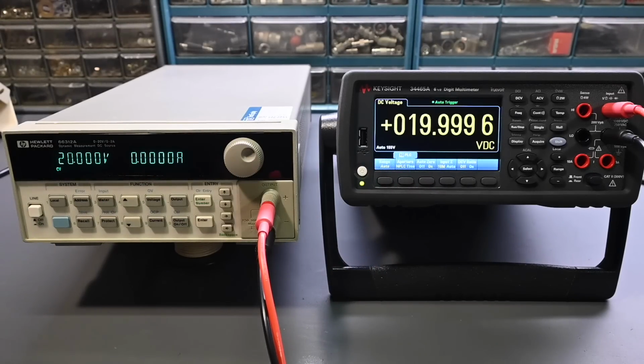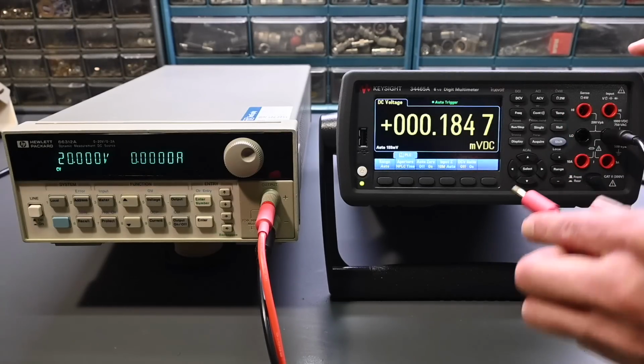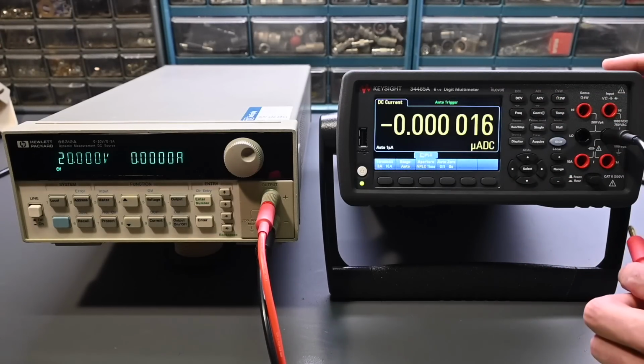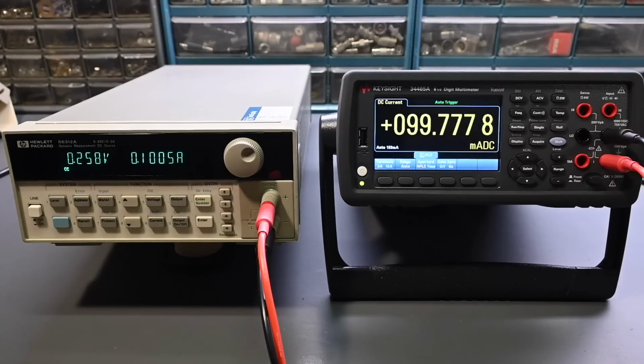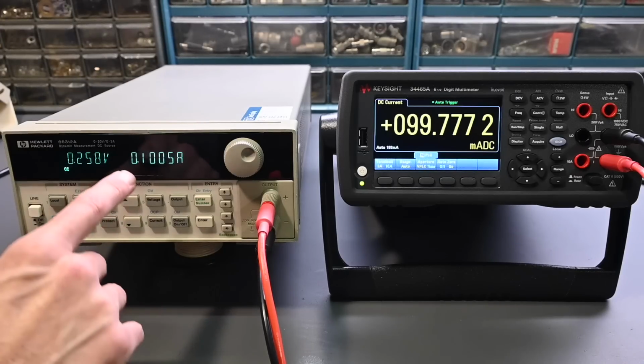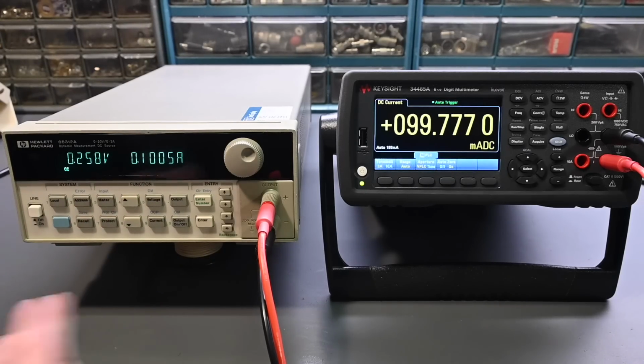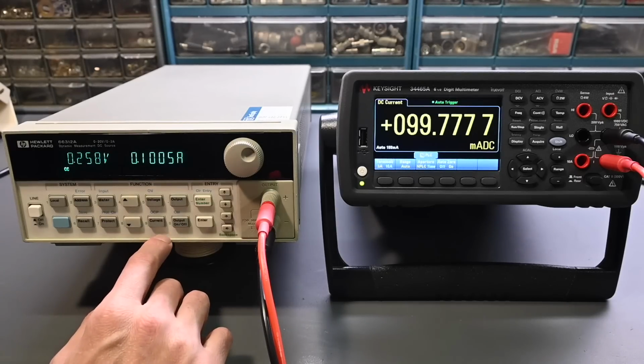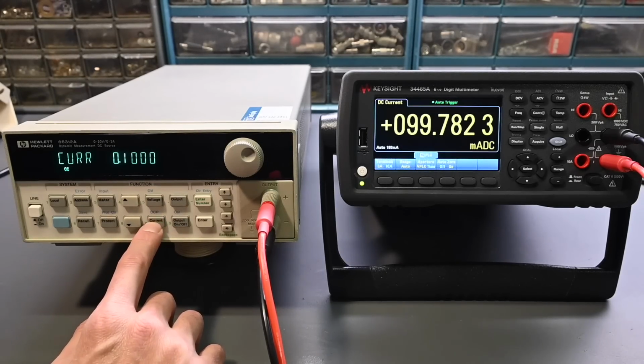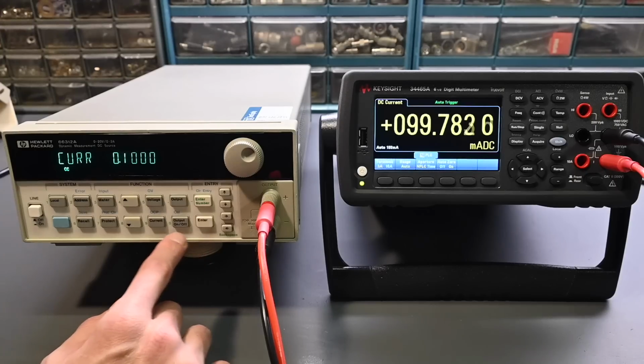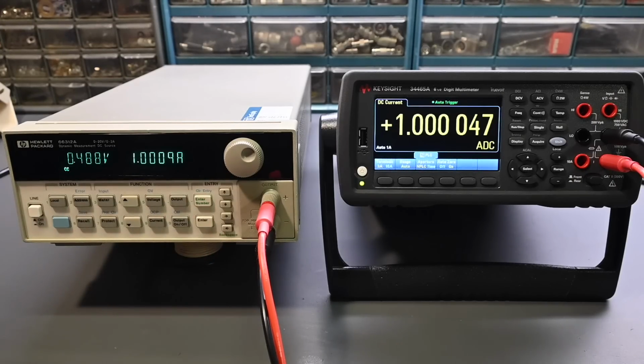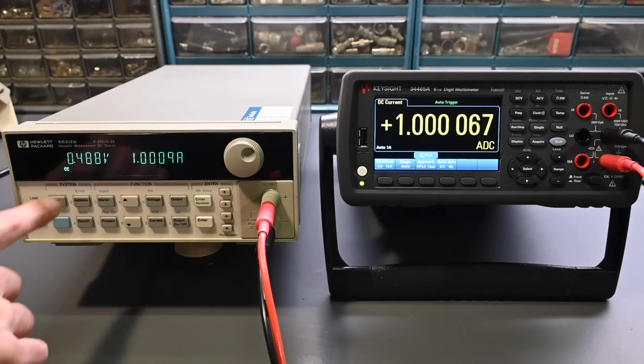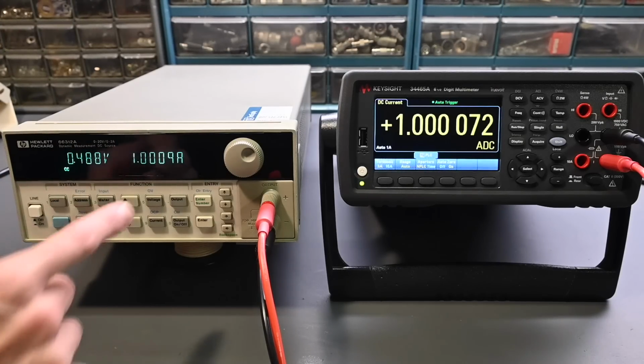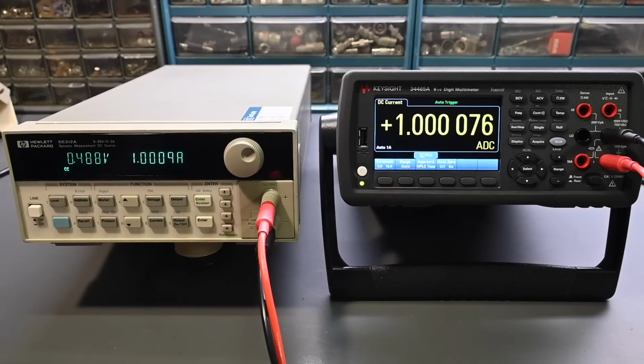So let me reach over here, and I'm just going to go down to this right here, DC current mode. All right, so right now it's current limiting at 100 milliamps, and yes, right at 100 milliamps over there as well. So if we go to the current setting, and let's go up to say 1 amp, let's try that. So enter number 1. So you can see how the voltage drops down. It's in constant current mode, so 0.488 volts, but it's holding right at 1 amp. And yeah, it looks very good over there, no problems with that.